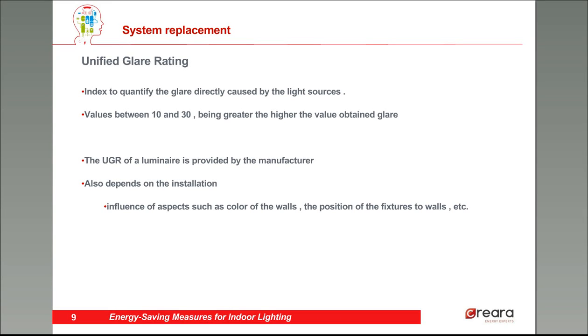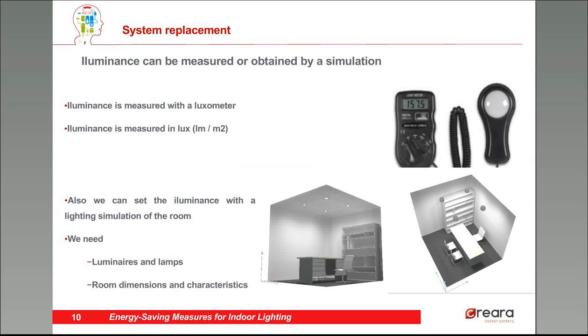The unified glare rating is the indicator to quantify the glare directly caused by the light sources. The values of this indicator are between 10 and 30 — the higher the value, the higher the glare of the luminaire. The UGR of a luminaire is always provided by the manufacturer, but it can change depending on the installation. The lighting level in a surface, or as we call it, the illuminance, can be measured or set with a simulation. We usually measure it with a luxometer, which is simple and cheap equipment, measuring in several points to establish the average illuminance in the room.